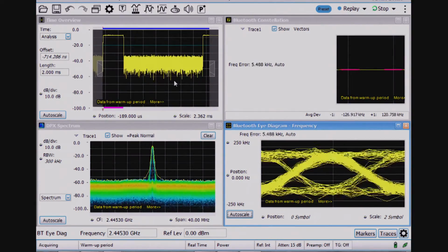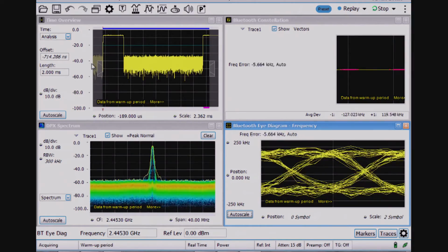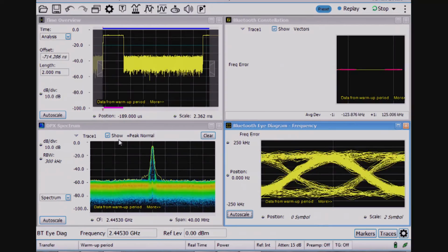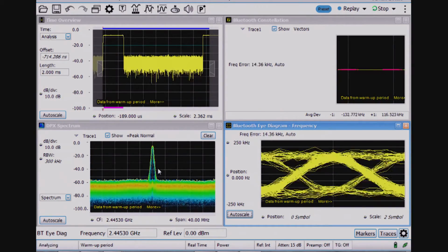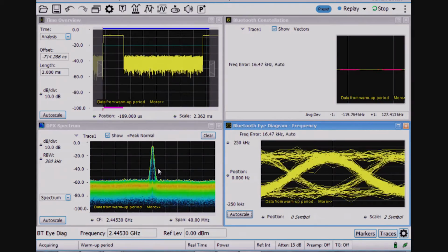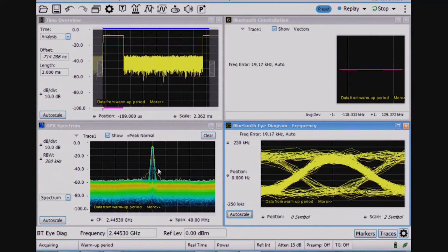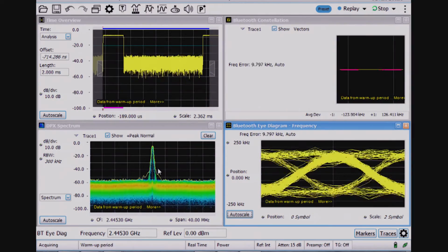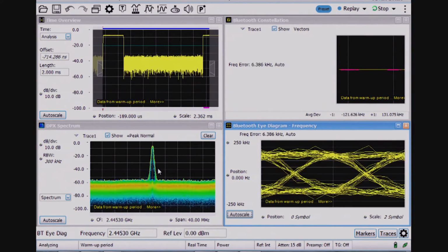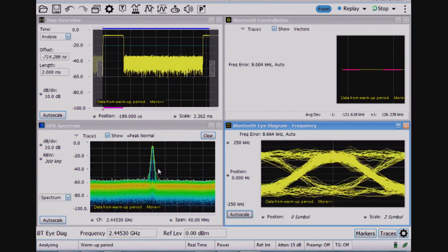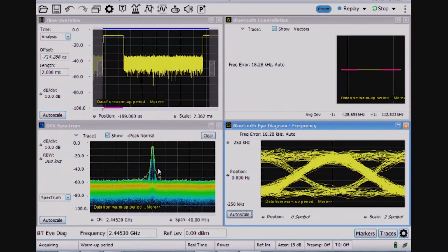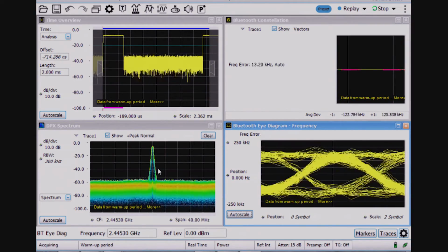And I can see pretty clearly the time domain part of the signal, the RF envelope, like a zero span display, and the time overview, and also can run the DPX spectrum concurrently as well. So that's basic measurements. Another thing that's worth noting is that if I want to perform programmatic measurements, if I want to automate these measurements, all these controls are available via programmatic interface through the SignalVu-PC API with the full programming manual that's also available.